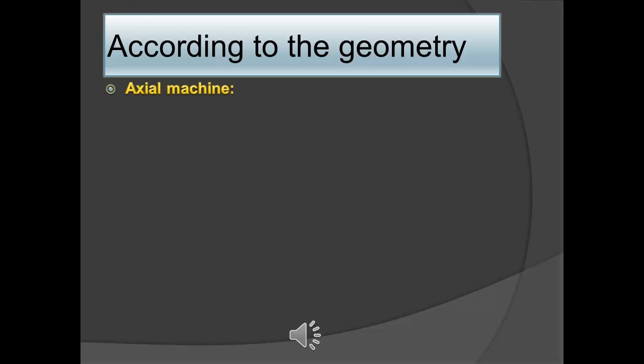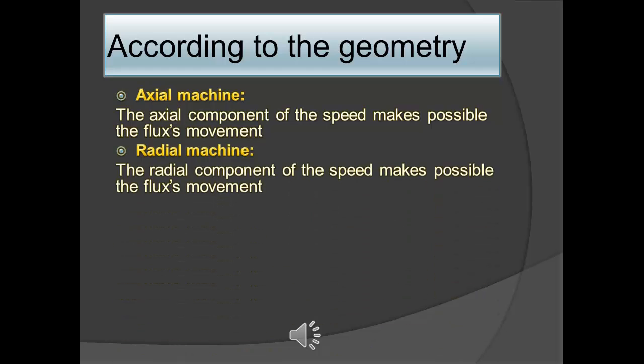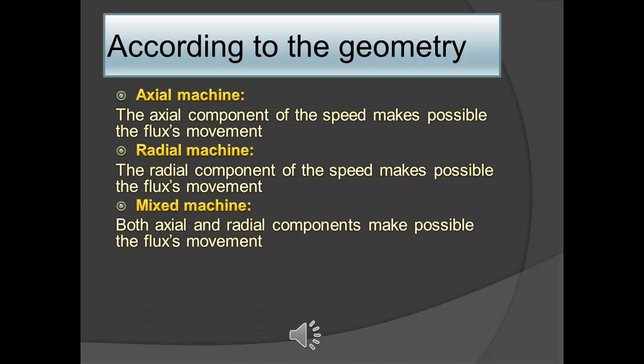Axial machine, where the fluid always goes through the impeller in the axial direction. Radial machine, where the fluid goes into the impeller and the geometry of the impeller changes the direction of the fluid and achieves that the radial component of the speed was responsible for the movement. And finally, the mixed machine, where both axial and radial components make possible the fluid movement.